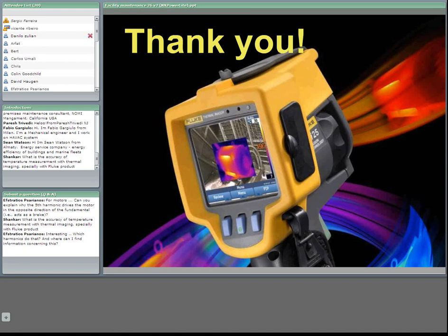Well, the problem of reflections can be avoided by placing yourself in another place. It's the same as a normal light reflection. By moving, you can avoid reflections. If you can't, if the reflections are, for instance, from the sun, then you should make the inspection during the evening or when the sun is not present. That will also take away the problem of solar heating.